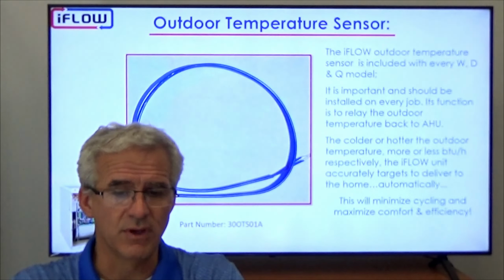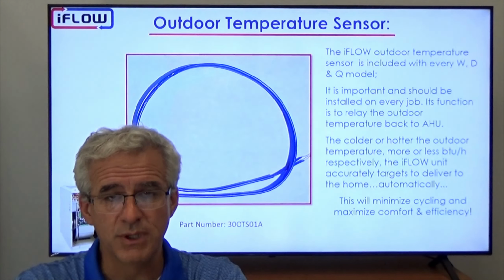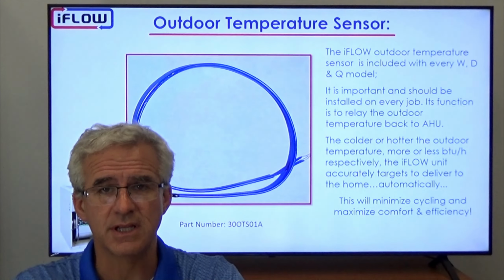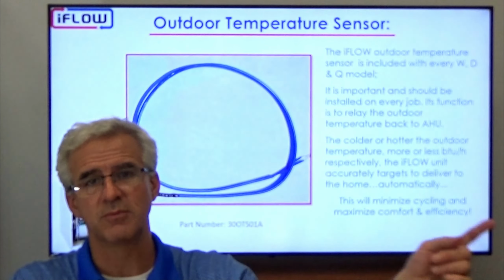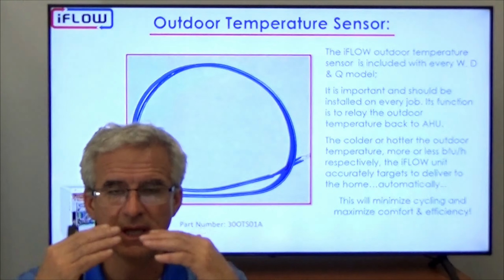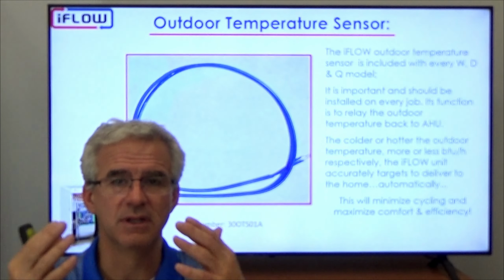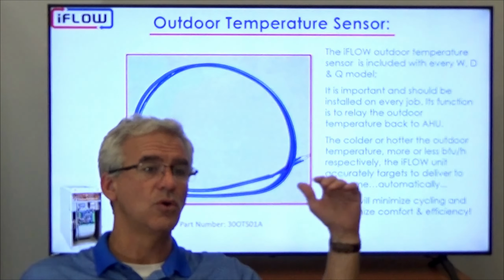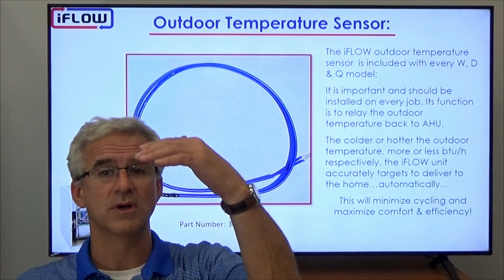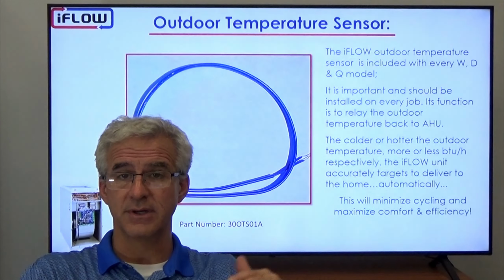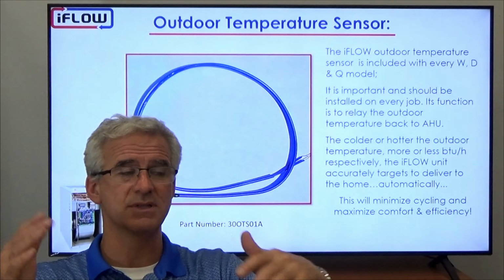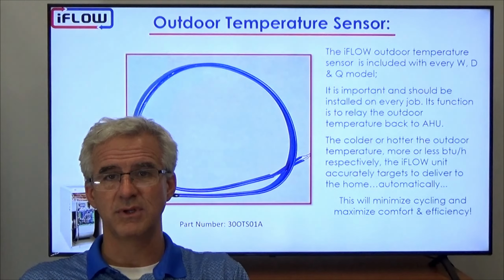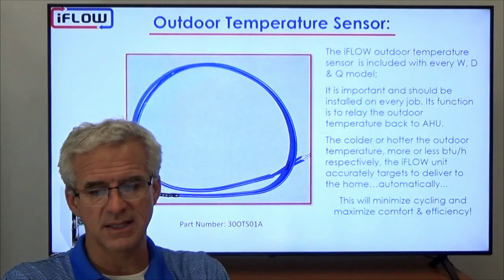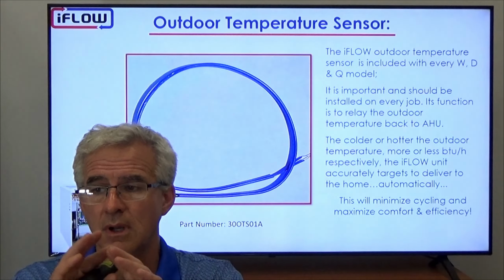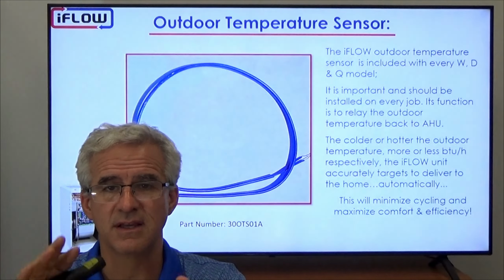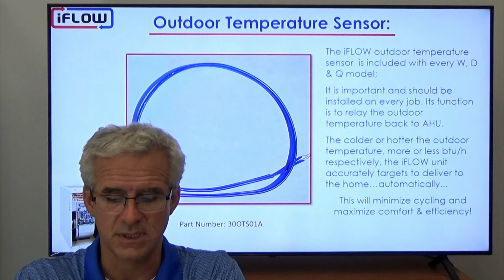So again, it comes with every unit. It should be installed on every job. Its function is basically to relay the outdoor temperature back to the unit so that we can adjust the BTU delivery into the house. So as it gets colder outside, we'll deliver more and more heat. As it gets milder outside, as we go from winter into spring, for example, it will reduce the amount of heat we deliver into the house. And it's all done automatically, so the homeowner doesn't have to adjust anything. They automatically get great comfort delivery into the house.